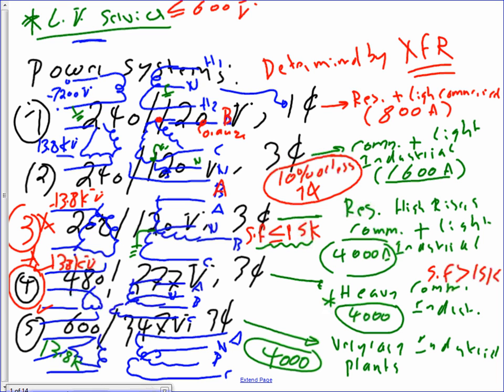So the first system, guys, it's a 7200. Can you guys see that? 7200, 240/120, the first one. This is single phase, typically used in residential and light commercial, and we typically use it up to 800 amp. So if you have a commercial building, light commercial building, or residential building, most likely you're going to have a system that's coming out of a transformer single phase, primary 7200, secondary 240/120. And it's going to be feeding residential and light commercial up to close to 800 amps. Sometimes they go higher than that.